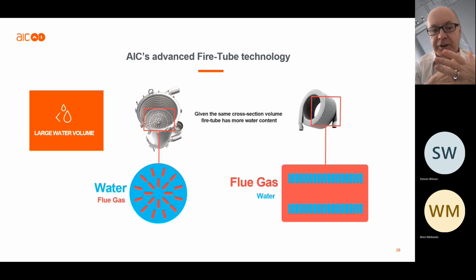And this is just demonstrating again larger water volume with the fire tube heat exchanger against the water tube. What that does, because you've got higher water volume, we've got more stability in the heat transfer process. So it's making the heat exchanger a bit more stable through the whole heat transfer process. Also, it helps with the pressure drop. So if I take, for instance, a 120 kilowatt boiler, the pressure drop going through that is probably about 60% less than it is going through water tube. So that helps with the sizing of pumps, etc.